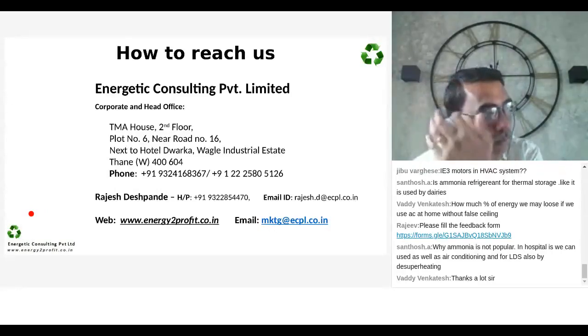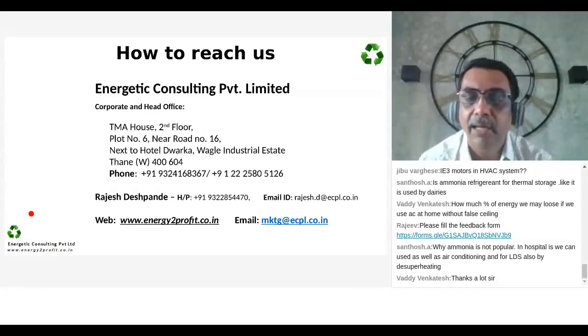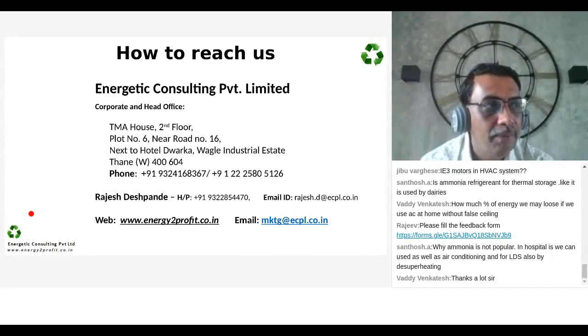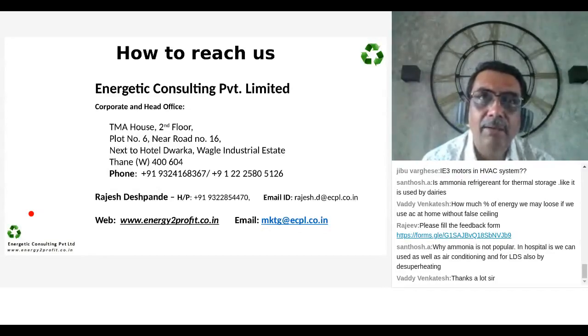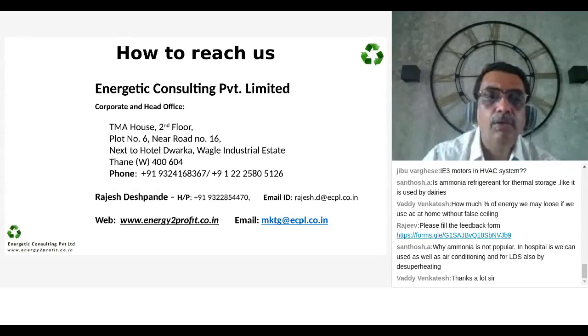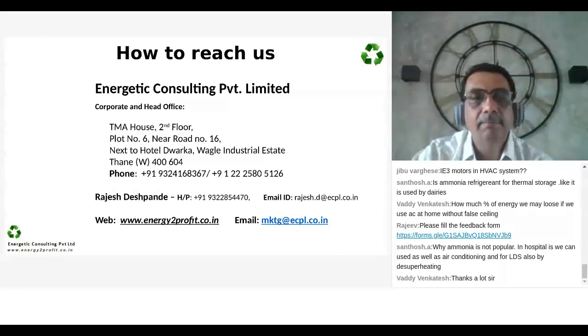In fact, Kalwa Hospital, where we made the change, had an ammonia system. You have a screw compressor based ammonia system. It is very well sealed. If you have reciprocating, then you have heads which leak, so there is a chance that it may cause a problem. So it's the smell and leakage that is the issue.